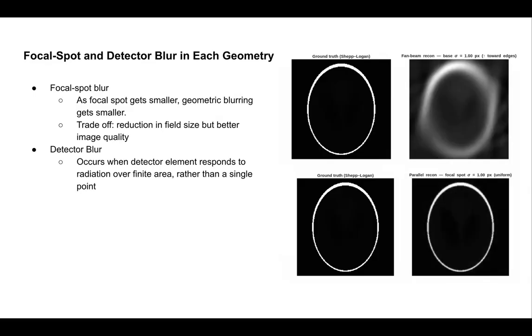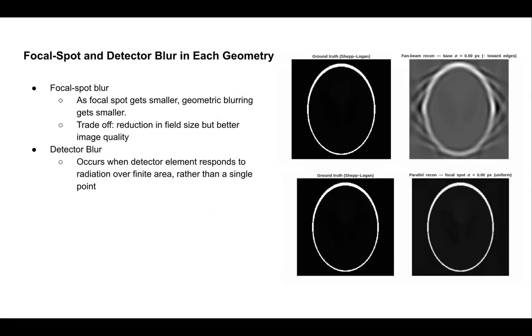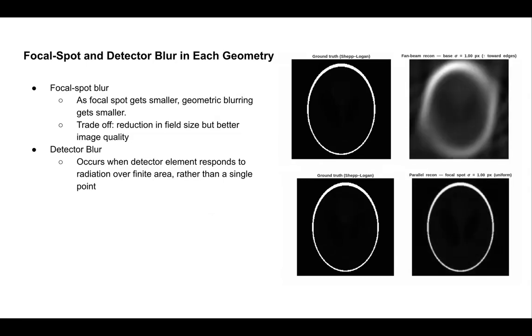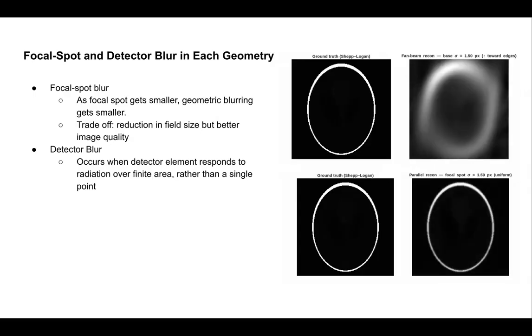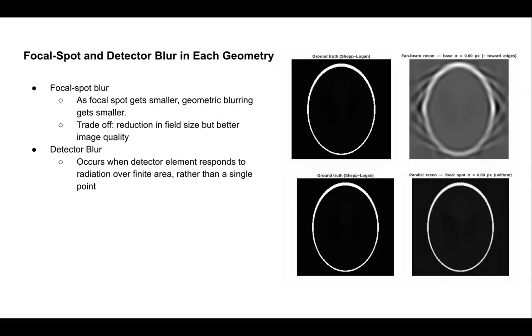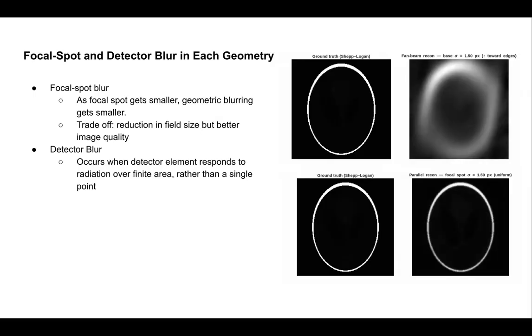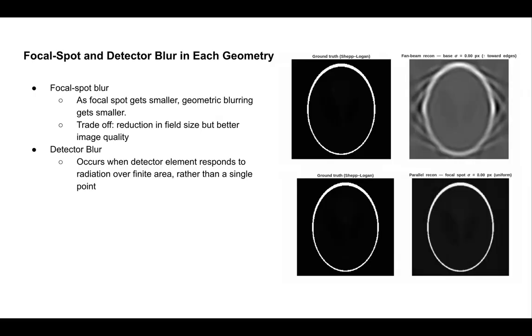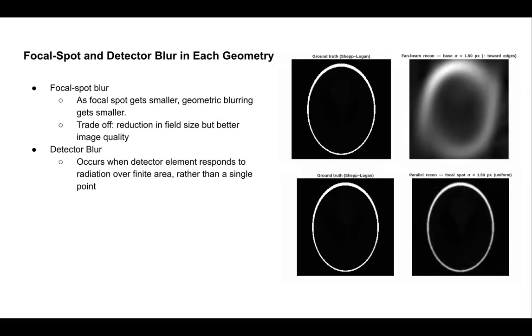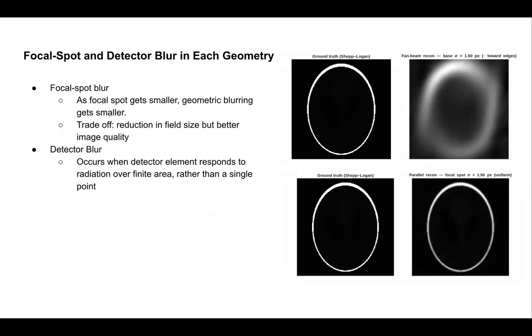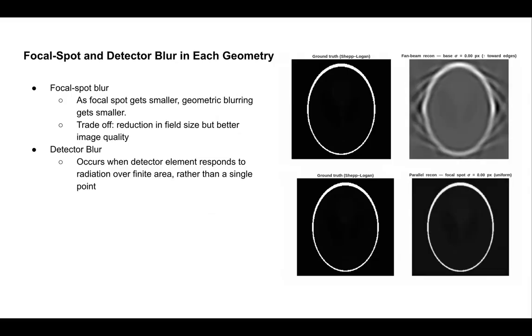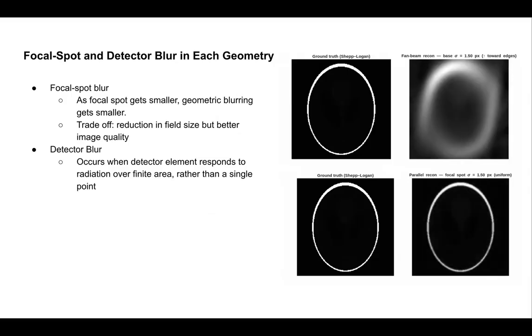On the MATLAB figure, the top Shepp-Logan phantom demonstrates blurring as focal spot size increases. Notably, the fan beam reconstruction blurs more at the edges. However, the bottom phantom reconstructed with parallel geometry blurs uniformly as focal spot size increases. This loss of edge clarity corresponds to a drop in the modulation transfer function, MTF. We'll quantify that next.